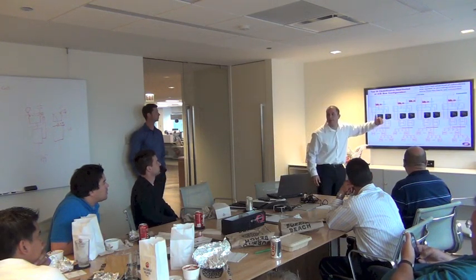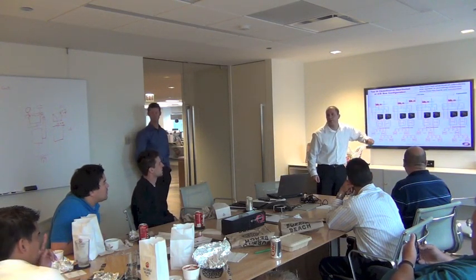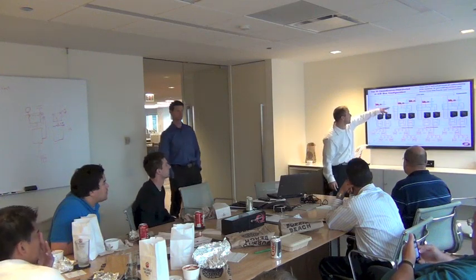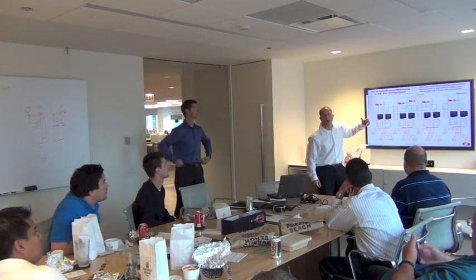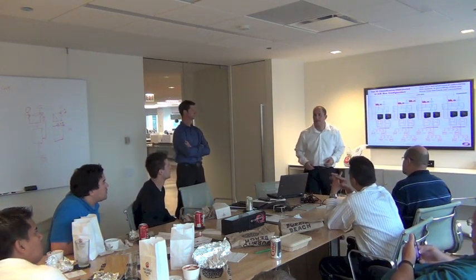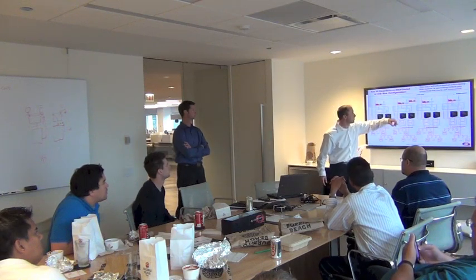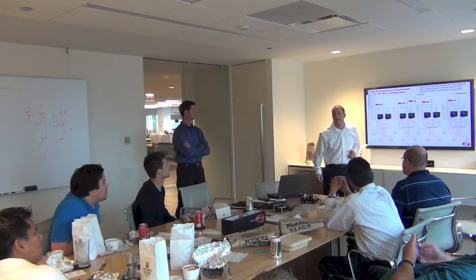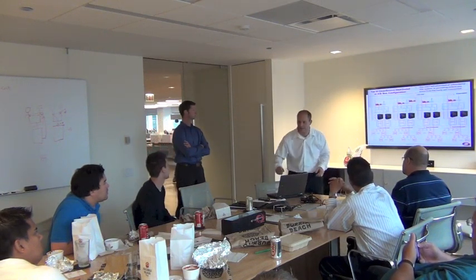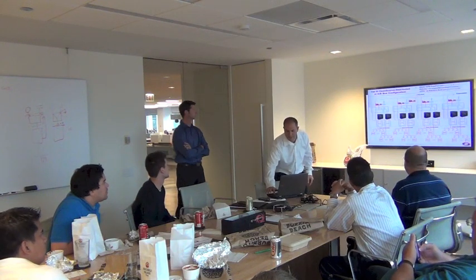We don't do a lot of massive amounts of paralleling. We do a lot of distributed redundant systems. In this case, we have 4 primary gens and a swing. In the event of an outage, we'll bring them all up at the same time. If any one of these isn't up to speed and voltage in a certain amount of time, we'll close that swing to the bus. And we also monitor them as they come up to see if anyone's lagging significantly.